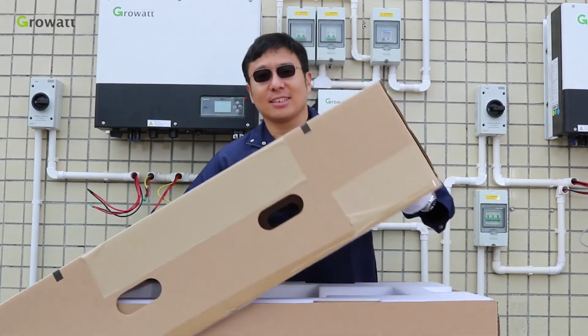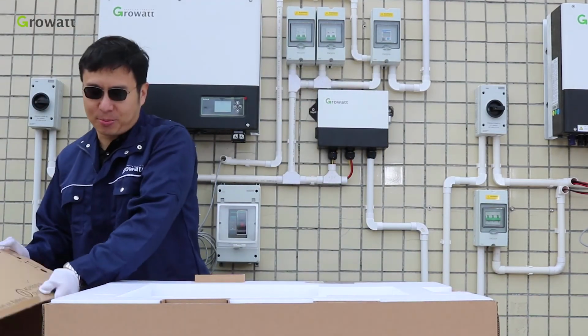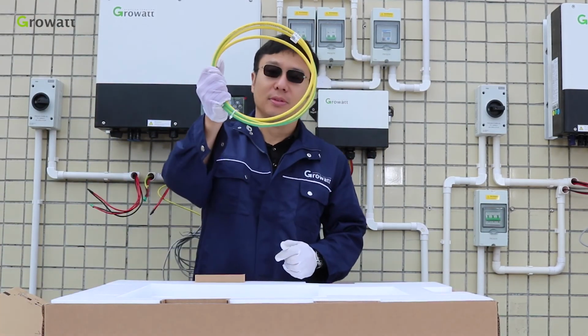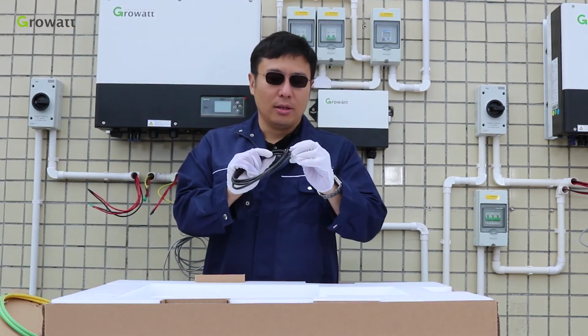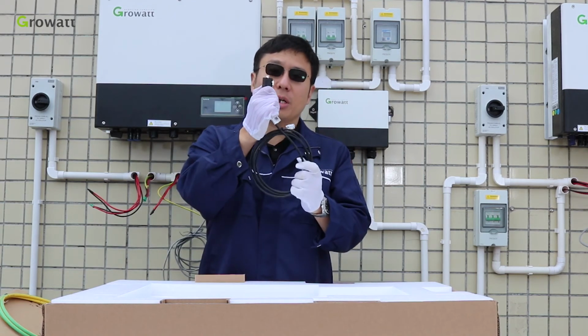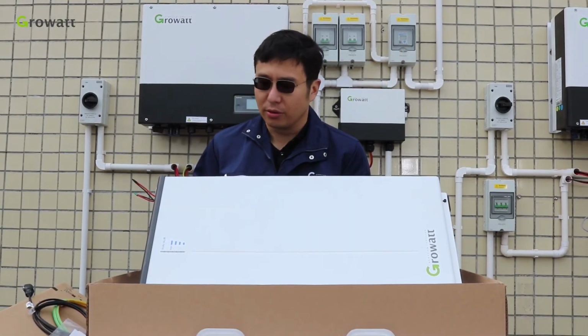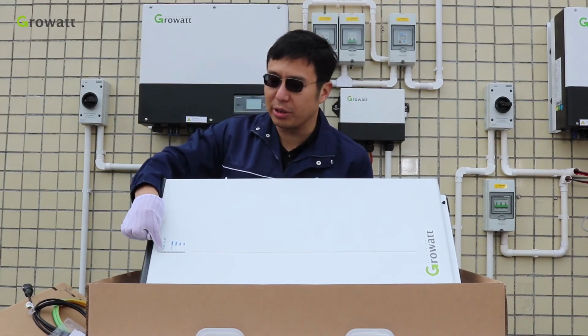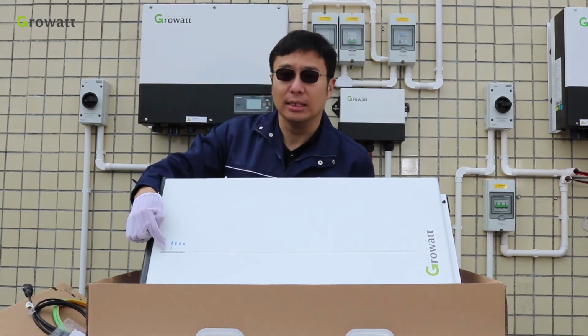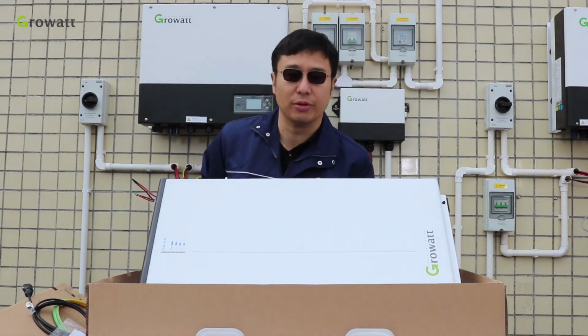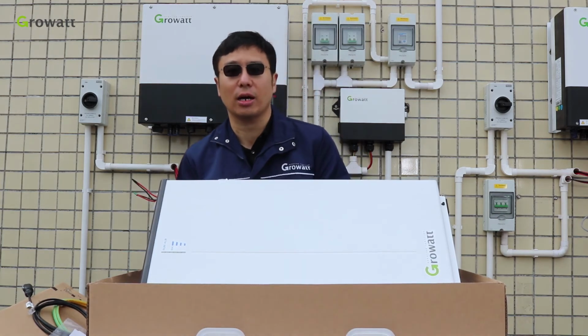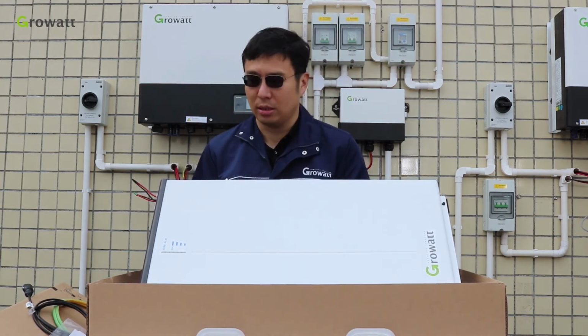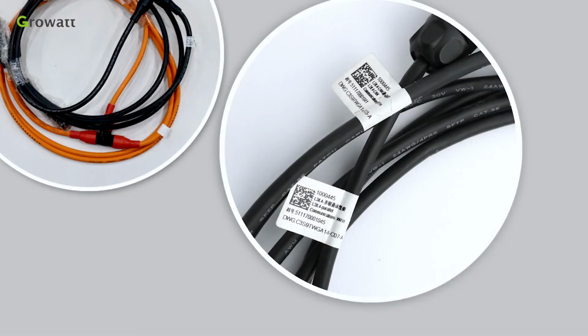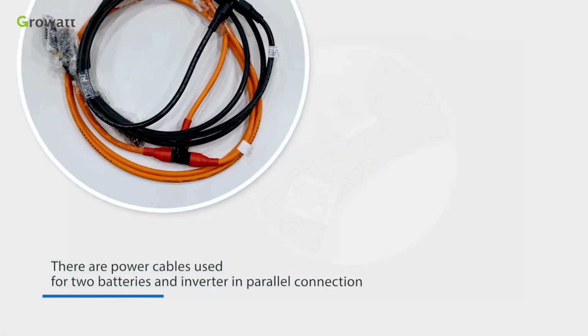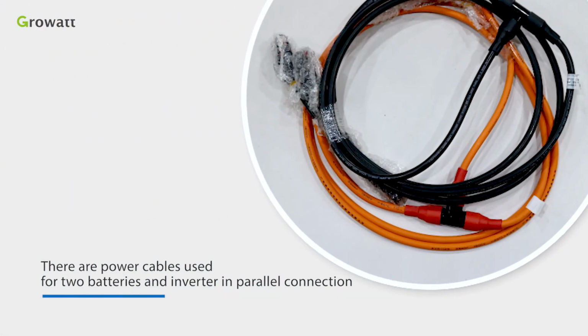Unpack the battery package, and there's some parts inside. Ground cable, communication cable between the battery and the inverter. User manual. This is GBLI 6531 battery, and here is the LED light for SOC of the battery. The battery system is 6.5 kWh and the usable capacity is 6 kWh. There are power cables used for 2 batteries and inverter in parallel connection.